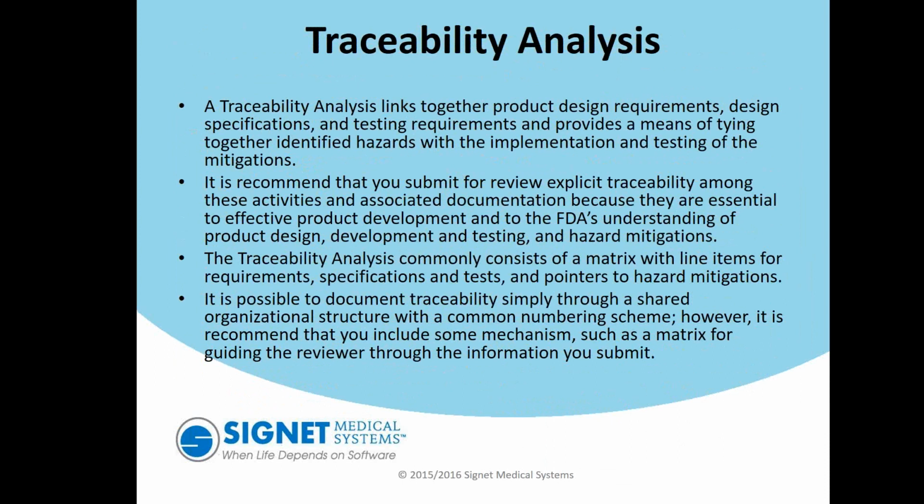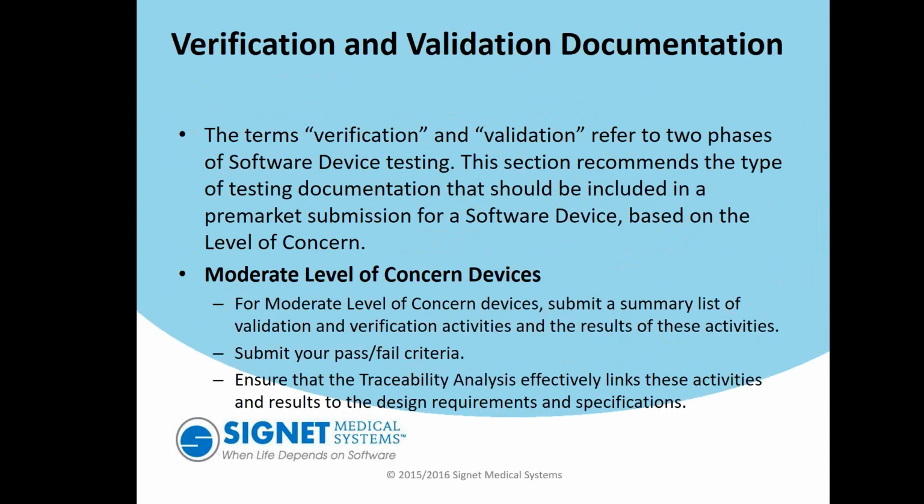You can just submit something that's kind of casual, but ultimately you want the reviewer to be very comfortable that you have actually designed what you said you designed. And part of that is because the FDA is somewhat skeptical about software, and you want to give the FDA the opportunity to say, wow, you've done a really good job, we're not going to even worry about it anymore. So anything you can do to give the FDA a good feeling that you are concerned about the risk possibilities in software really is a good way to ensure your 510K gets a faster track.